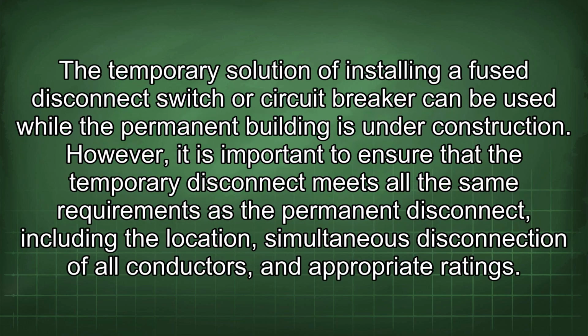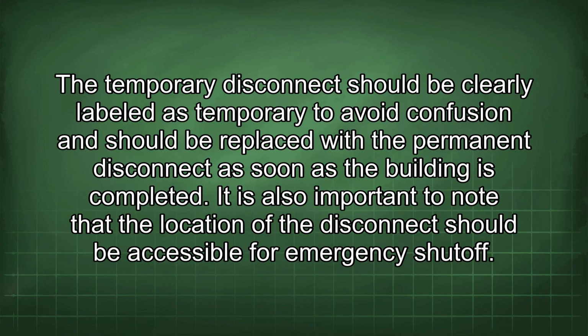A temporary solution of installing a fused disconnect switch or circuit breaker can be used while the permanent building is under construction. However, it is important to ensure that the temporary disconnect meets all the same requirements as the permanent disconnect, including the location, simultaneous disconnection of all conductors, and appropriate ratings. The temporary disconnect should be clearly labeled as temporary to avoid confusion and should be replaced with the permanent disconnect as soon as the building is completed.